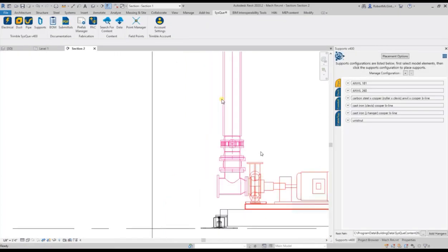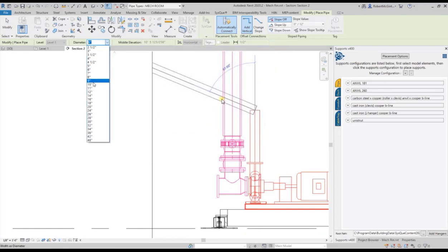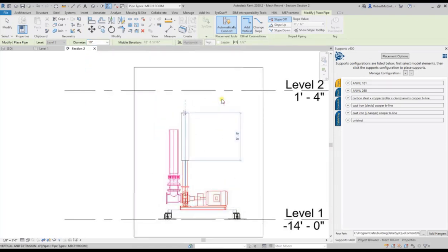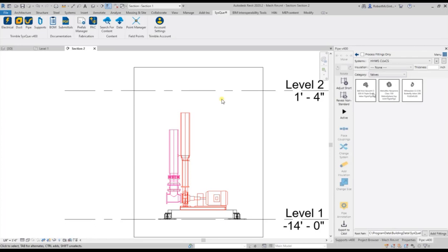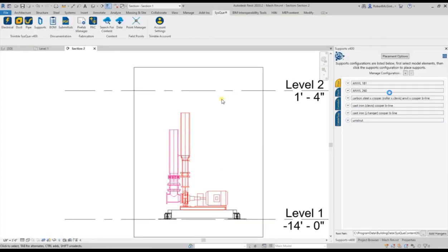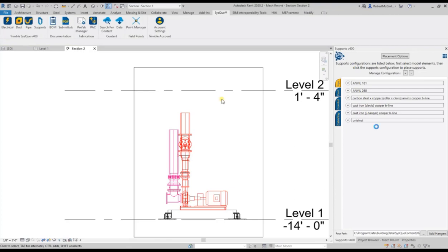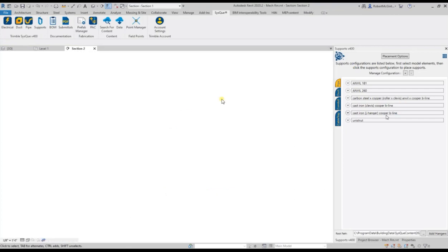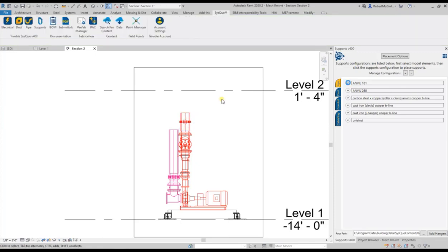Now you're on the hot water side, and one of the things I like is the elevations that you're spotting in your section, right? Tell us what those elevations help you do when you're in the plan view and start to route that pipe above those pumps. Yep. So the elevation is going to be set. You'll see me here when I'm done putting in all the valves, I'll go back, click on both pipe supply and return and figure out my elevations so that when I go to the top view, I can cut the pipe in. And when I draw the pipe, all 3 of my T's will be automatically cut in. I don't have to go select T's, resize, or any of that. They'll all be cut in.